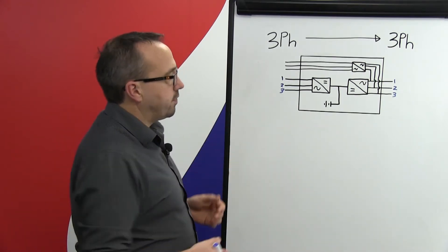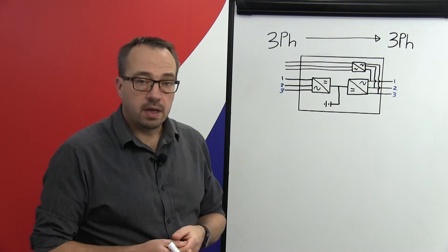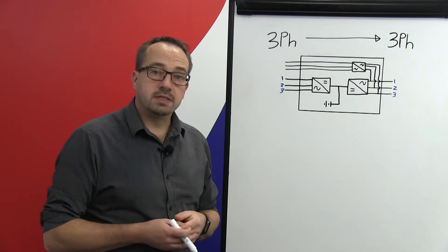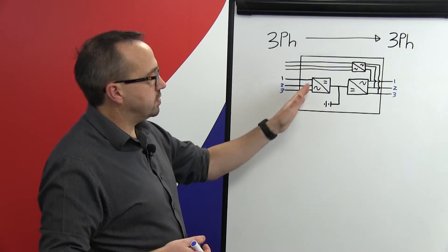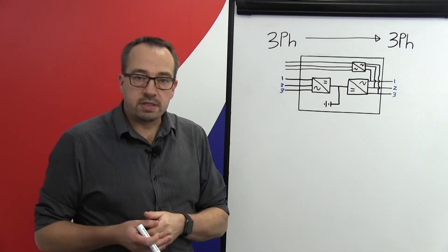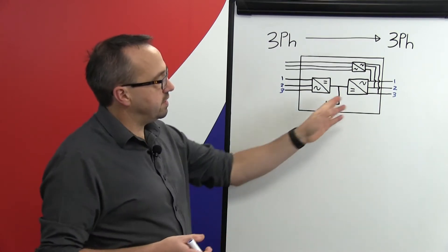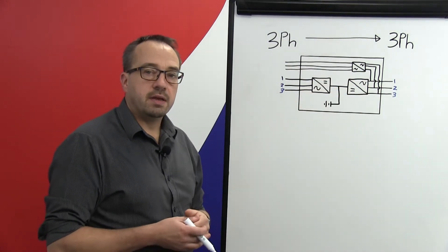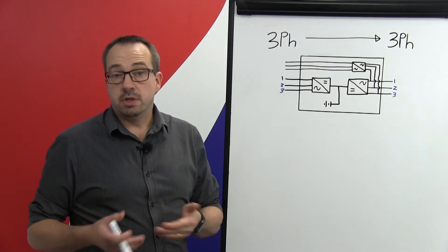Now on the board here we have a very basic diagram of an online dual conversion UPS system. The online dual conversion UPS system operates simply by taking the AC voltage from the main supply, converting the AC voltage to DC voltage via the rectifier which is referred to as the first conversion. We then reconvert that DC voltage back to AC voltage again via the inverter which is referred to as the second conversion and hence the term dual conversion.